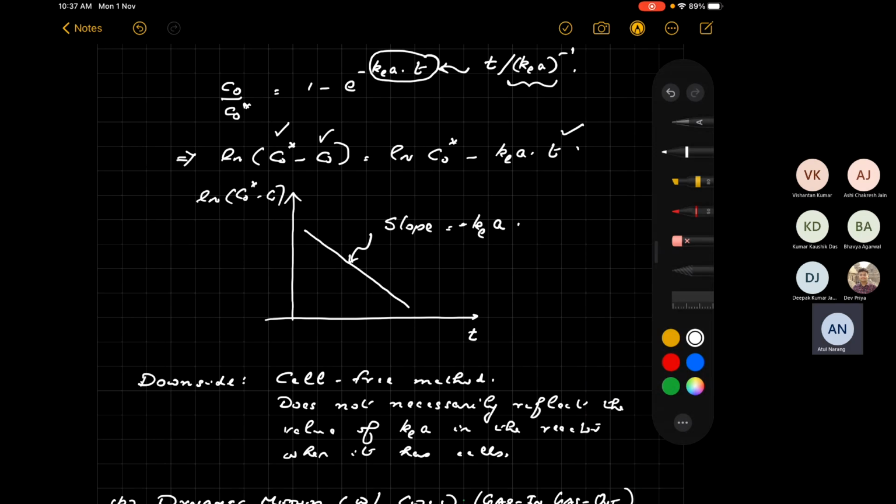This is because the DO probe itself takes some time to give you the reading. Why? Because as I mentioned to you, the oxygen has to diffuse across a membrane and get to the cathode. Now, this may take 10 seconds, 15 seconds. So the reading that you are registering right now is actually the concentration in the aqueous phase 15 seconds ago. You're not getting real time data. You are getting data with a slight lag. This lag can actually have disastrous consequences for your measurements.